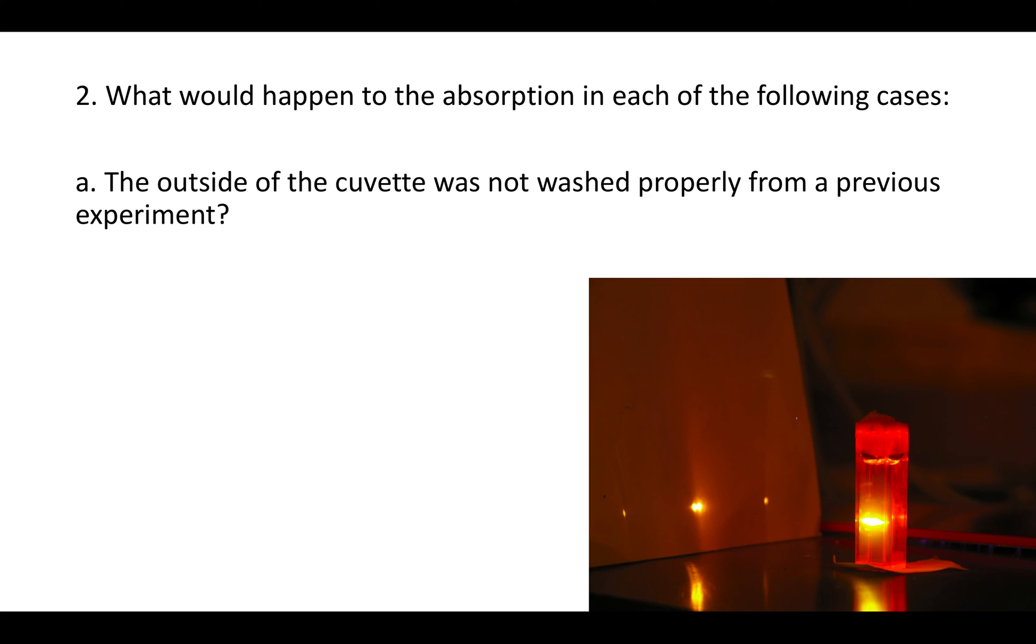If you handle the cuvette, your fingerprints, the oils on your hands, form a thin layer of oil on the outside of the cuvette and that oil will absorb some of the light. And so that will add to the absorption of the compound and you'll get a higher absorption and a lower transmittance of light than you otherwise would have.